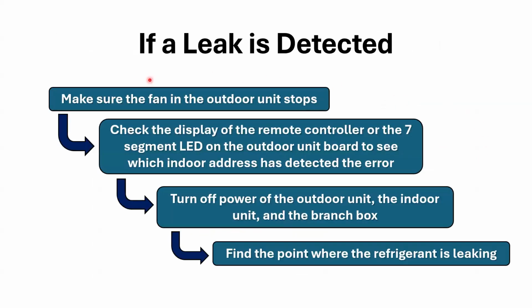All right, so if a leak is detected, make sure the fan in the outdoor unit stops. Check the display of the remote controller or the 7-segment LED on the outdoor unit board. See which indoor address has detected the error. Again, it depends where you're going when you show up, outdoor unit first or inside the home first. And if you see the controller and you see FL on it, and the address, you're there. So you're going to get the error in both locations.